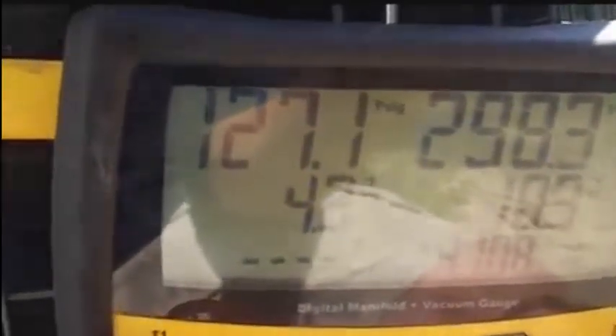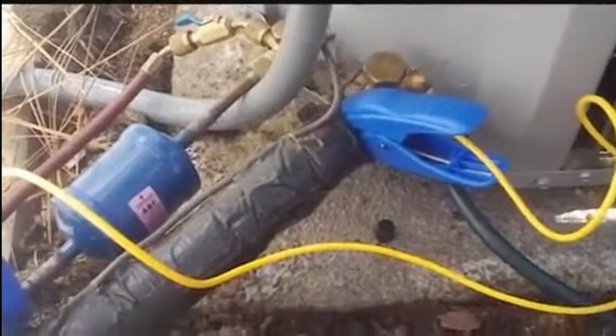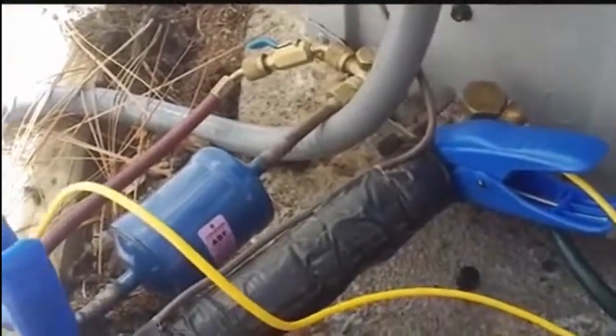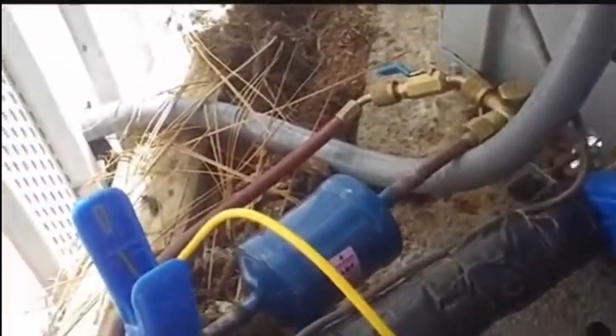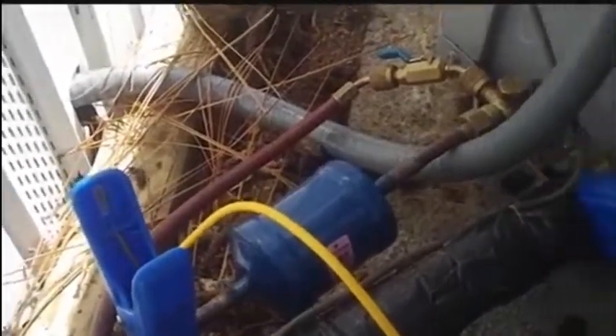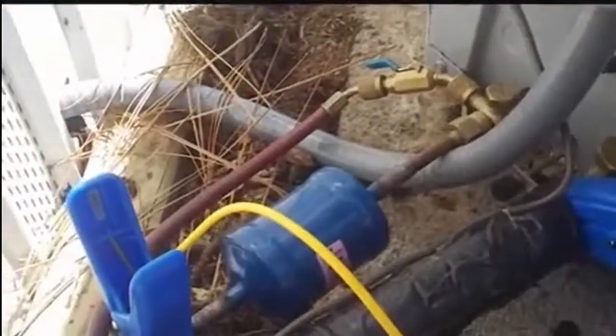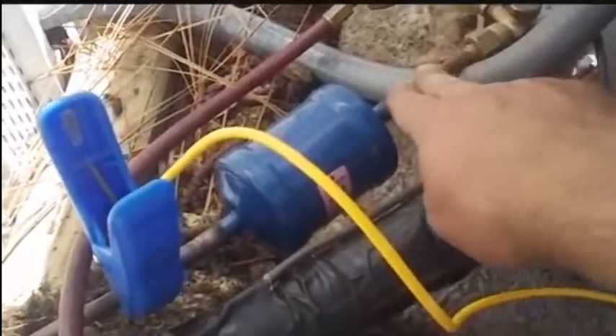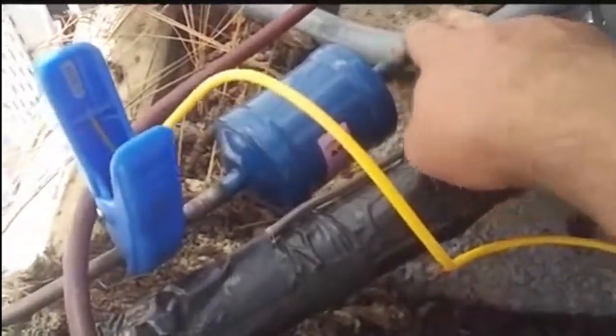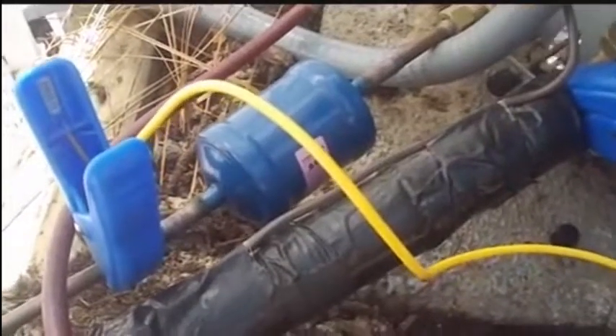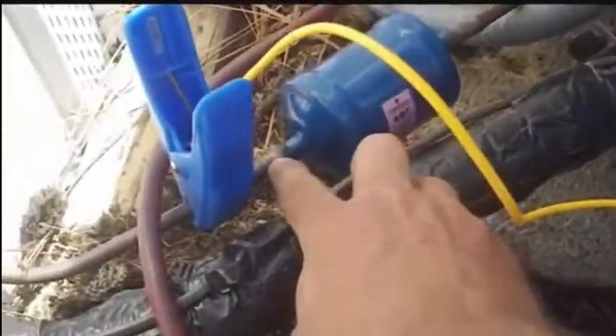So we're pretty squared away. I'll let it run for a little bit longer, but we're probably not going to alter anything. She looks pretty good, and she's getting 20 degrees inside, which is pretty good. A couple guys had asked me about where you put your clamps for the S-Man for measuring superheat and subcooling. So where I put mine is for subcooling, you're measuring the subcooled liquid heading out of the condenser right here. So once it leaves the condenser, the 3/8 line typically with residential, you put it anywhere on this line going back toward the evaporator. Usually at the condenser, that's where your gauges are at, obviously.